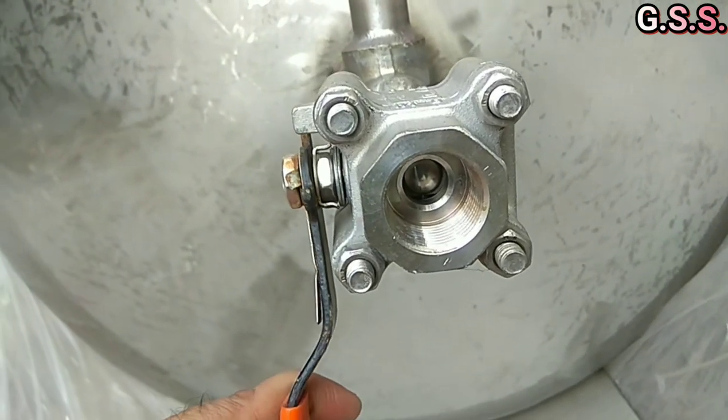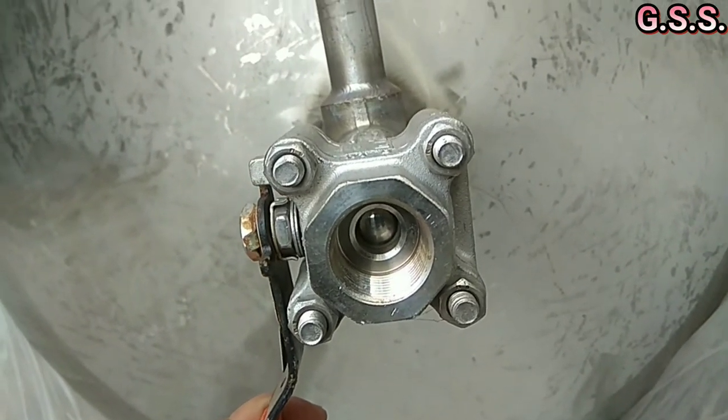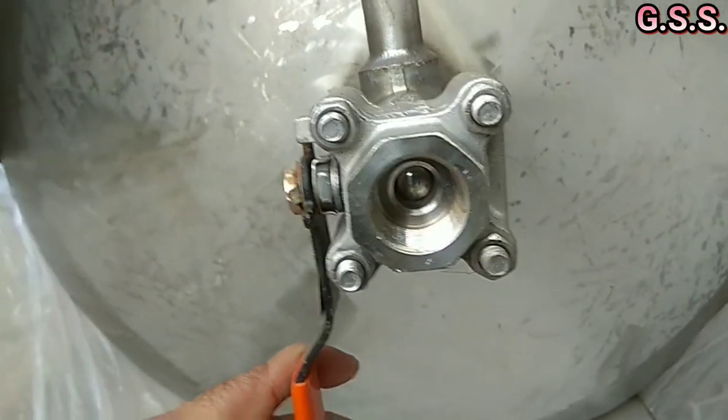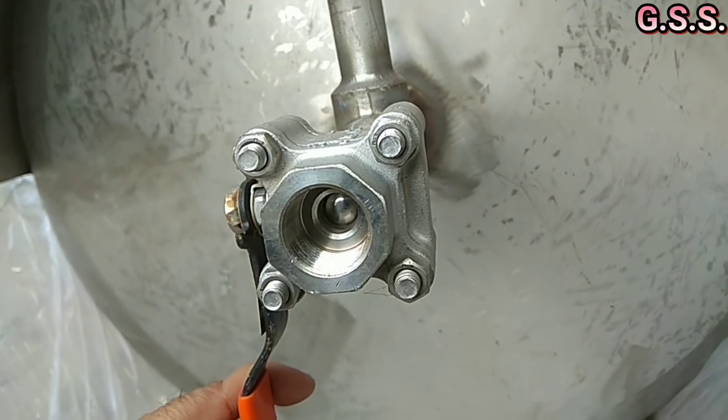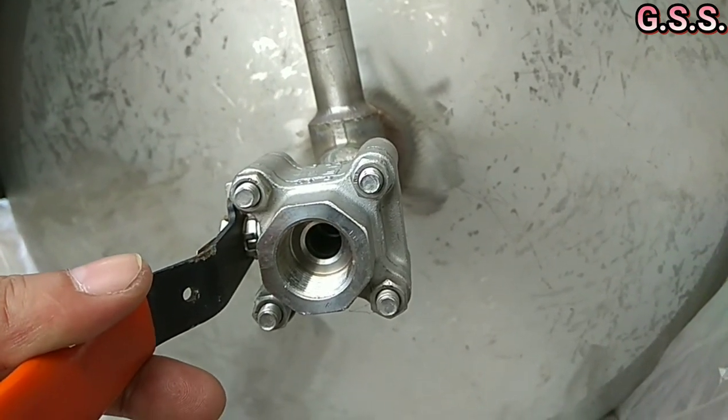Through this type of reduced bore ball valve, flow velocity will be higher and pressure drop will be greater. Also, due to the reduced bore, debris or particles will accumulate in front of the ball.